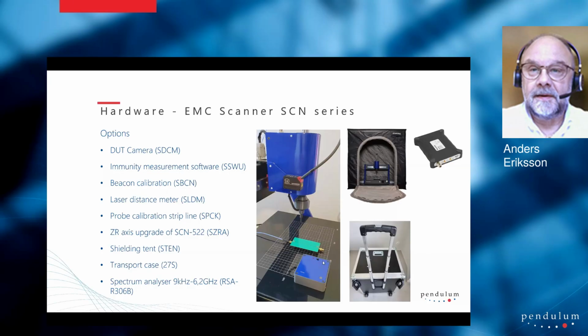Beacon calibration. It's this blue box down here. It contains 3 small beacons, and it allows us to very accurately calibrate the X-Y position of the probe, not to the physical center of the probe tip, but to the electrical center of the probe tip. This is necessary if you want to do very, very accurate measurements. Normally, if you measure with 1 millimeter steps, you probably will not need this one. But if you want high accuracy, this is really good to have.